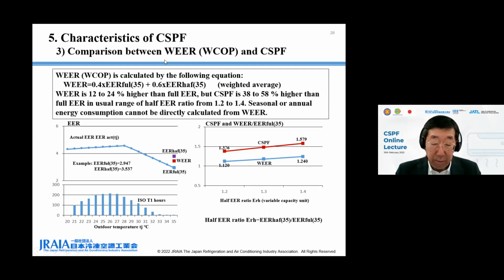This page shows comparison between WEER or WCOP and CSPF. WEER is calculated by the equation here, which is a weighted average of 40% full EER and 60% half EER tested at 35 degrees C. The upper left figures show full and half EER tested and calculated WEER at 35 degrees C and actual EER calculated at each outdoor temperature, TJ. For this example, half capacity ratio CRH is 0.5 and half EER ratio ERH is 1.2.